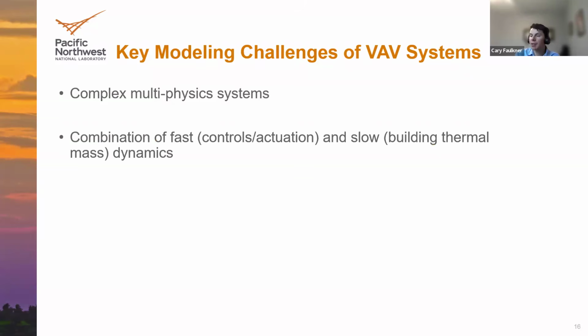There's also these different aspects of faster dynamics, for example, the controls and the actuations of those controls, with slow dynamics, like for the building thermal dynamics, which are going to tend to be inherently slow, especially for high thermal mass buildings. And this can create some numerical challenges as you want to be able to capture some of those fast dynamics to faithfully model the actuation of the VAV system, but you also have these very slow dynamics going on as well. There's also the pressure flow coupling, which I highlighted as important to model for these systems to really capture that relationship between the dampers and the fan, in a sense, how that informs what the fan is doing to provide enough airflow to meet the demands of the zones.